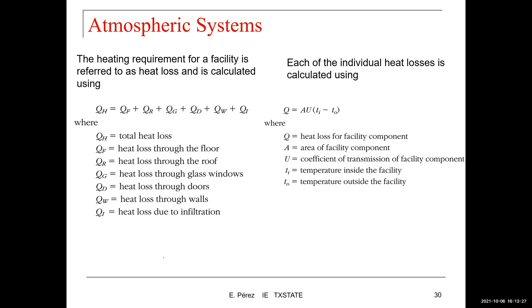And then for air conditioning, we have a similar strategy. We can compute the requirement for a facility, referred to as the cooling load, and that's obtained from this formula. The total cooling load involves the cooling load due to the floor, the roof, the glass windows, the doors, the walls, due to ventilation, due to solar radiation, due to lighting, and also due to the personnel inside the facility. So the cooling loads for the floor, the roof, the glass windows, the doors, the walls, and the ventilation are determined in the same way, using the same formula that we were using for heating.